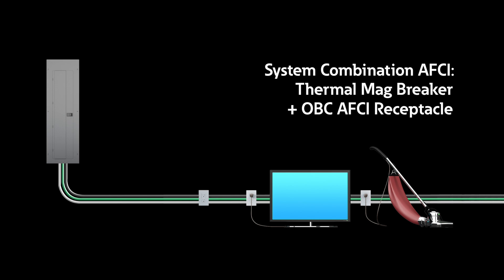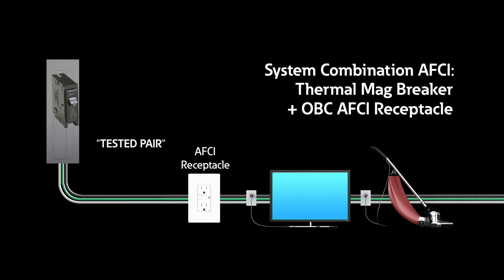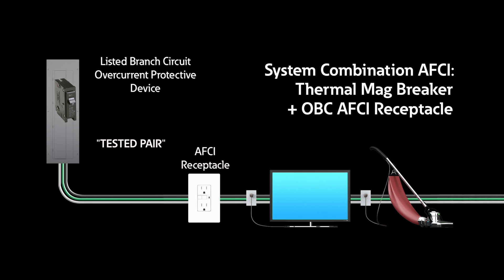System combination AFCI thermal mag breaker with an OBC AFCI receptacle. This is a listed, tested pair that includes an OBC AFCI receptacle installed at the first outlet on the branch circuit in combination with a listed branch circuit overcurrent protective device installed at the panel. While this installation allows for local reset capabilities, tested and listed combinations of AFCI receptacles and upstream branch breakers are not currently available. Additionally, there are limitations in the home run length.